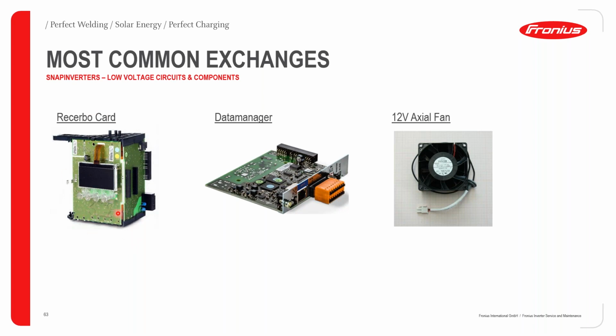Starting with the receiver card, this is the display card of the Fronius inverter. What's also very important to note is this little print, called the memory print. This print stores the inverter serial number, what type of inverter it is, and how many kilowatt hours this inverter has produced. Whenever you replace a receiver card, make sure that you break this print and put the old print on the new receiver card. It's kind of like the unique identifier of the inverter.